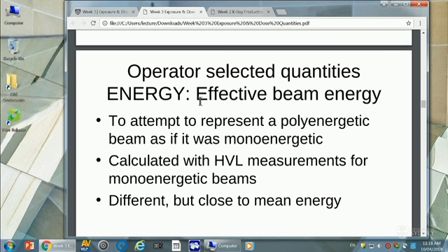Now, I'll just go over that again because people do get a bit confused. Yes, you can do that. You can't change the half value. You can change the filter. You can add to the filter. No, these values are written in stone. Scientists have done this and they've proven that the half value layer of an X-ray beam at this sort of keV is that. If you wanted to change your keV value, say you were currently working with something around 63 and you wanted to change it to 83, how would you implement that?